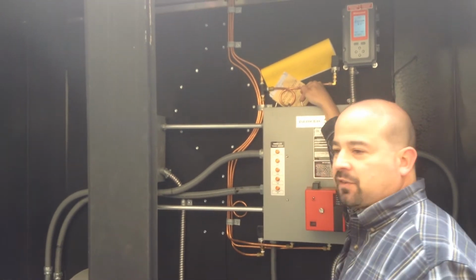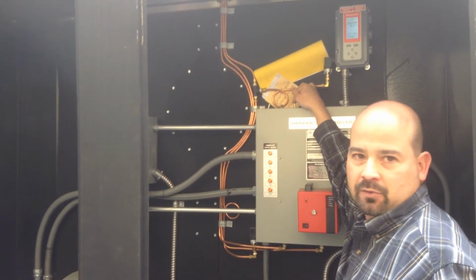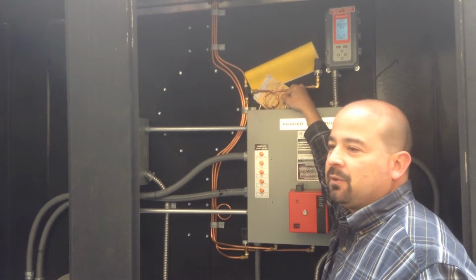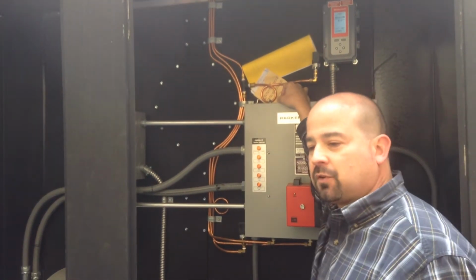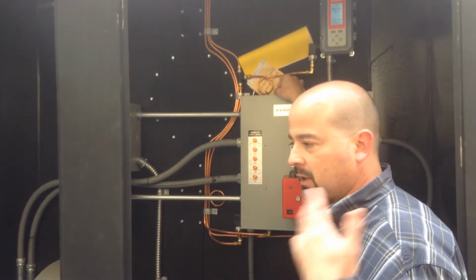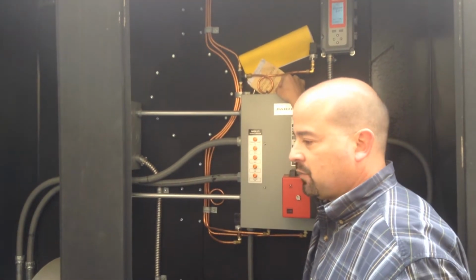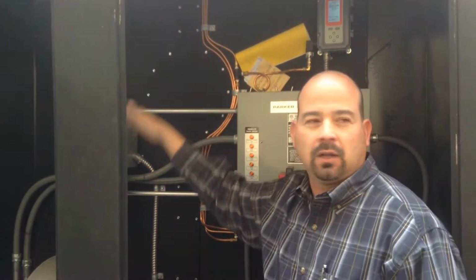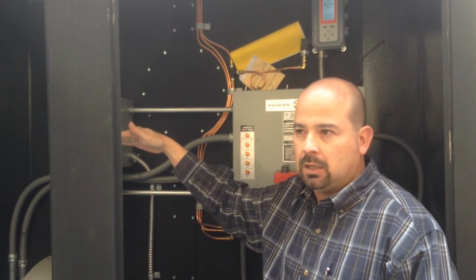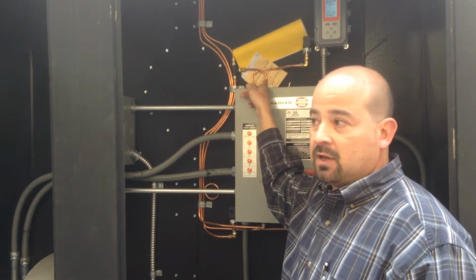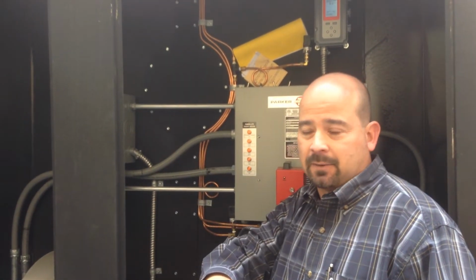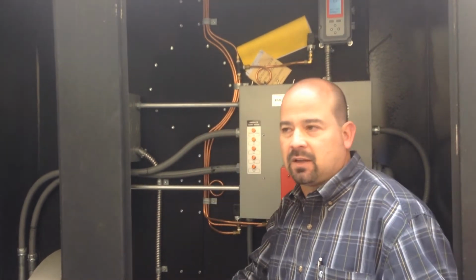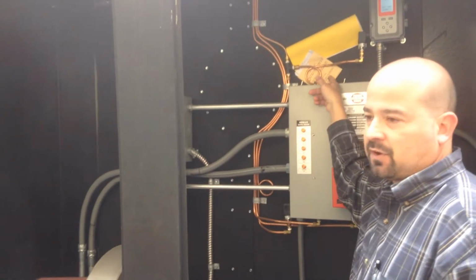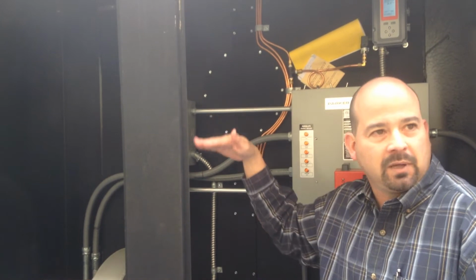You've got this switch that I just turned off right now. This is the burner switch. I typically recommend, when you need to turn the boiler off, like I just did because I wanted to be able to hear each other, or if you just want to do something but you still want the water level to work and be where it should be, just turn the burner switch off. If you're ever going to turn the boiler off at night, or you're doing some gas shutdown work, anything, just turn the burner switch off. That way the water level still goes where it should be.